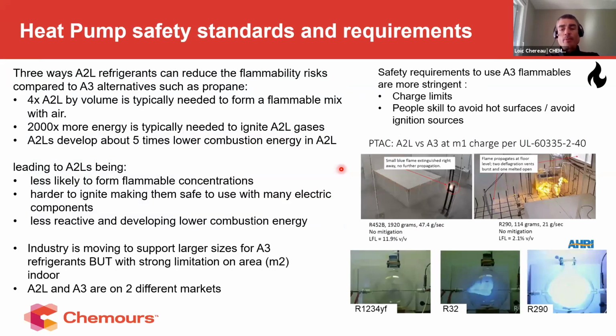Moving on and gearing up more on the difference between the A2L and the A3 refrigerant, mostly propane, because this is one of the very popular refrigerants being developed today on new equipment. The reason why the industry is still greatly considering the A2L refrigerant is because of the much lower flammability risk there is using an A2L refrigerant.